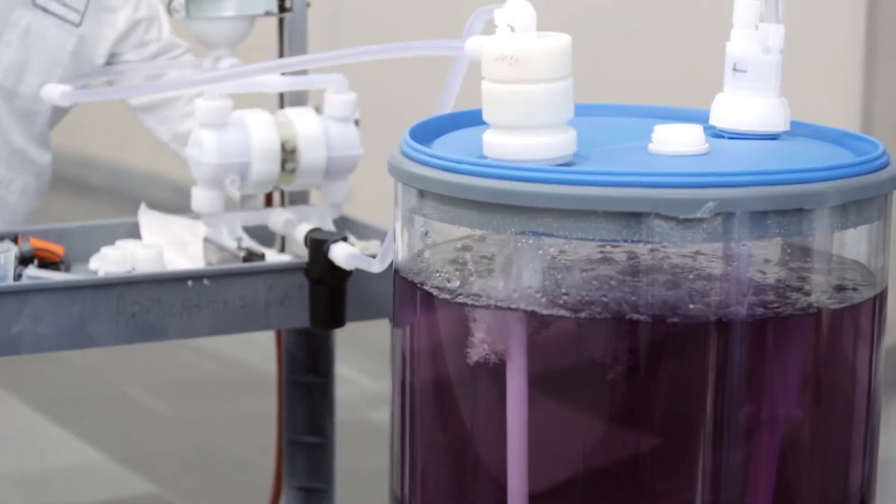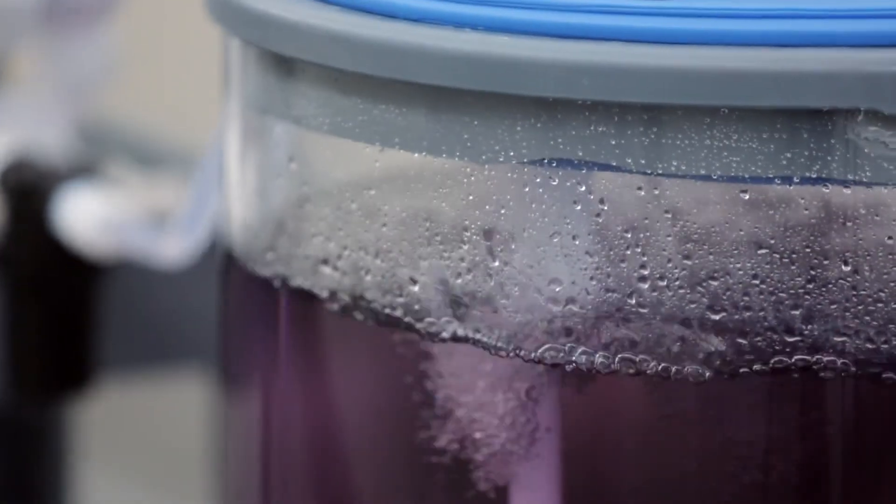As you can see, there's still a little bit of foaming, but it's not nearly as constrained. It's not nearly as high pressure as what you'd see on the QC2 design. This, again, would be suitable for slurries that have settling characteristics where you'd want to have mechanical agitation but didn't have any concern about foaming.